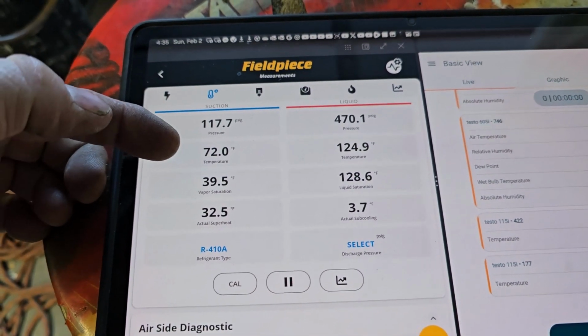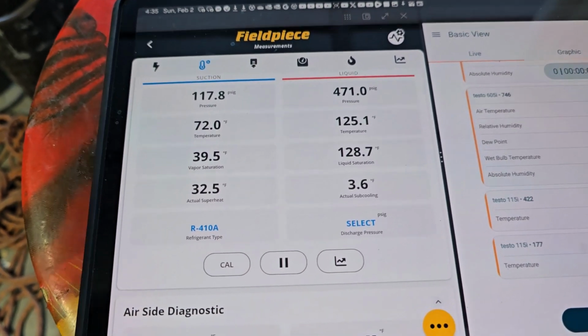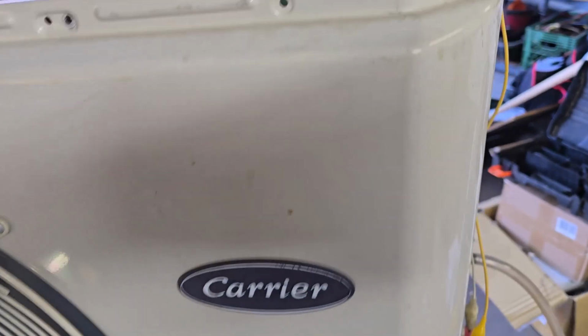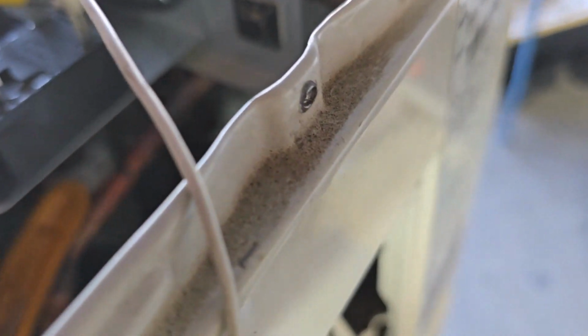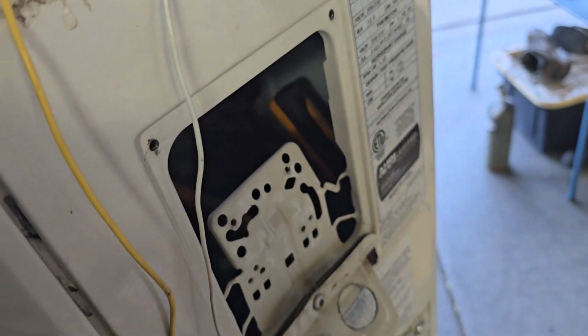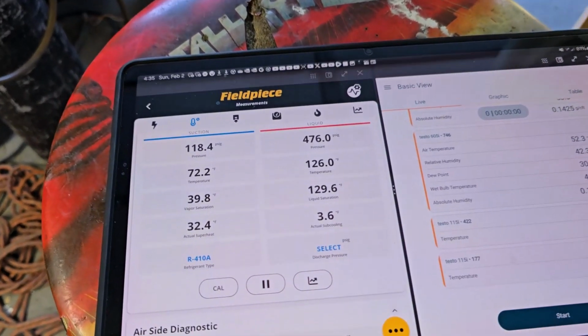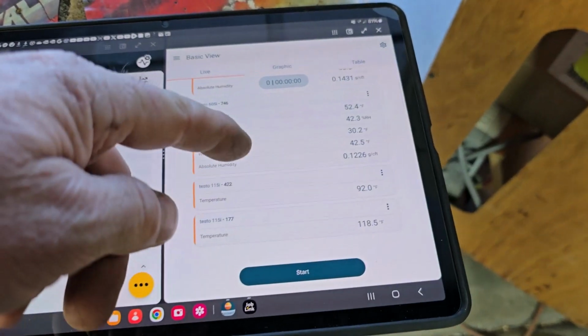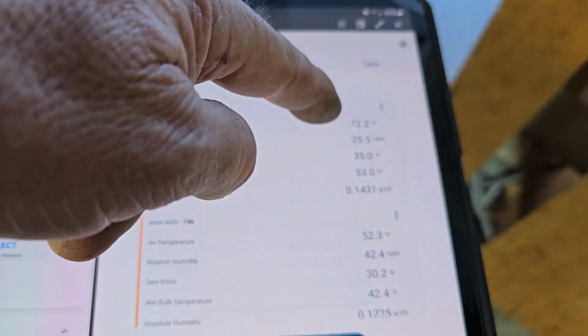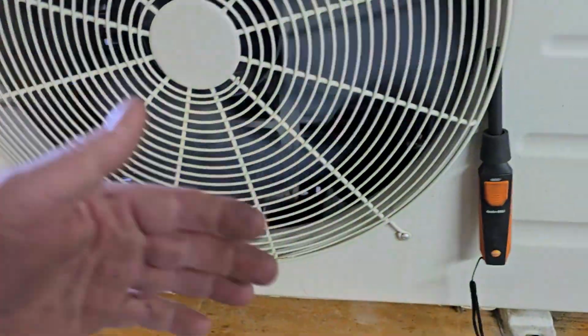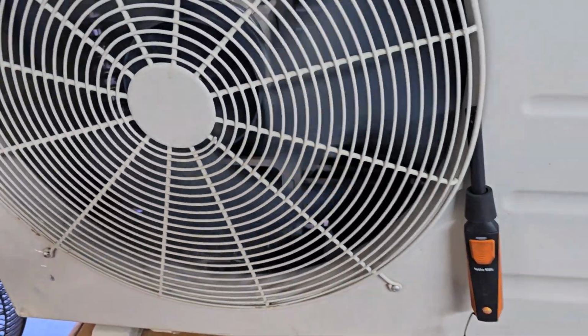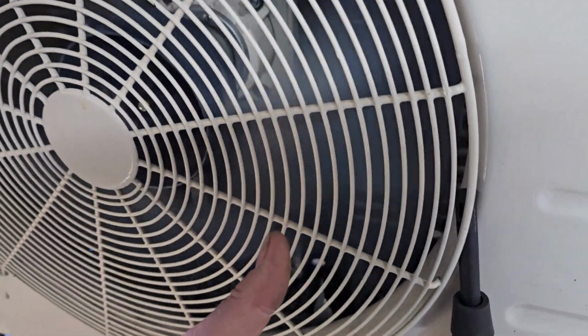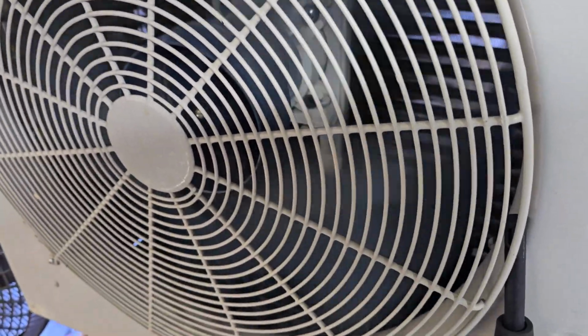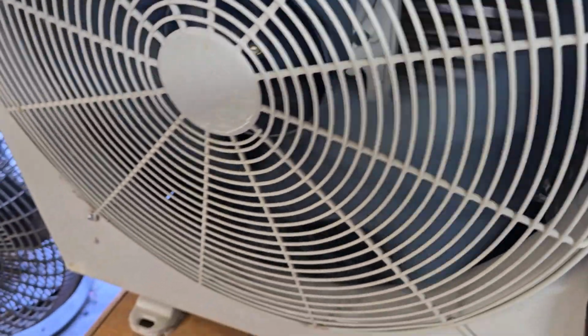That suction temperature felt pretty good earlier when I just put my hand on it. Obviously, it's like 72 right now. That's in a good spot. Yeah, it's not as cool as it was earlier, so it might take a little bit. But you can see the air temperature is going from 72 to 52, where the fan speed just happens to be, which is pretty good. Want to keep it just enough to move enough air and then be efficient.